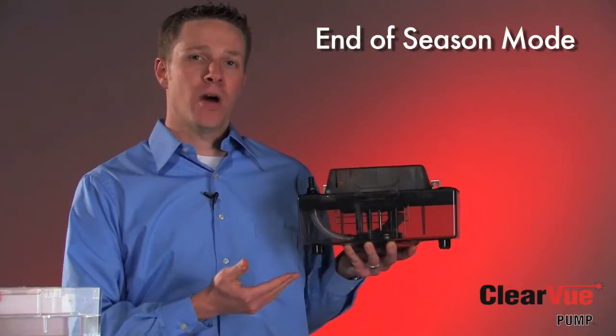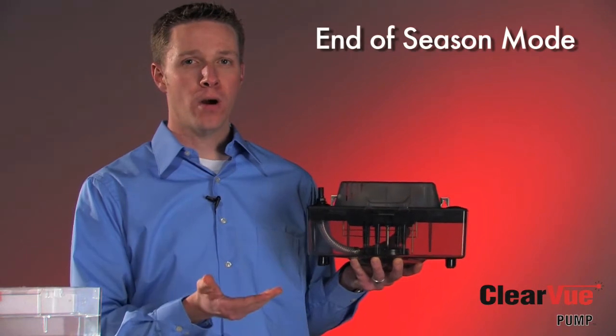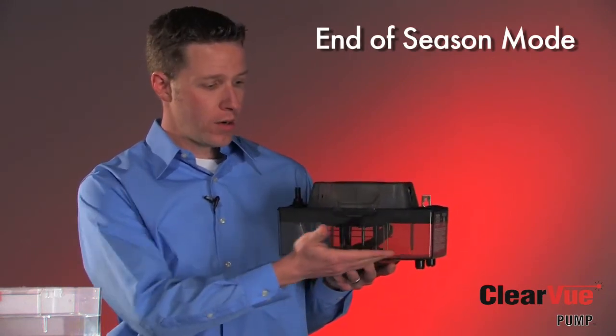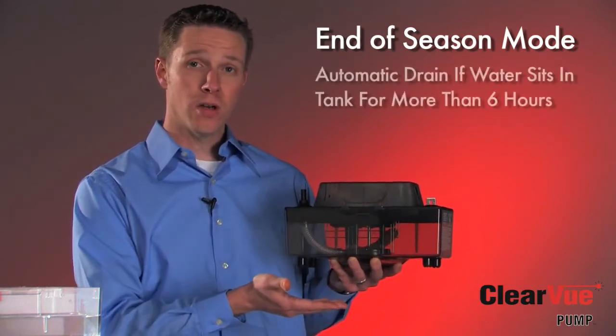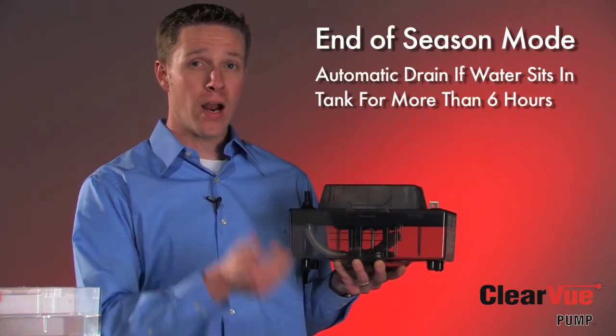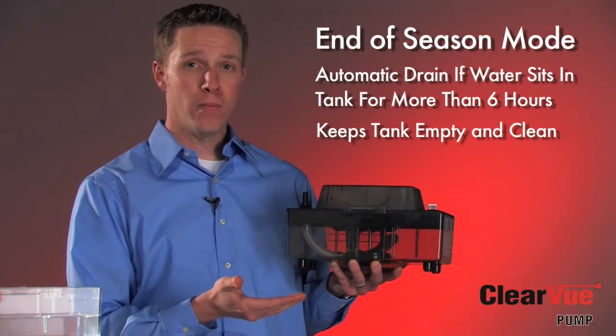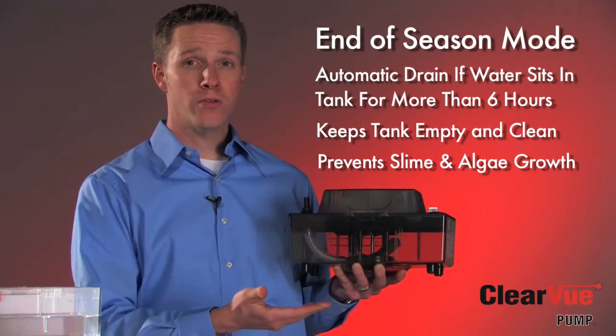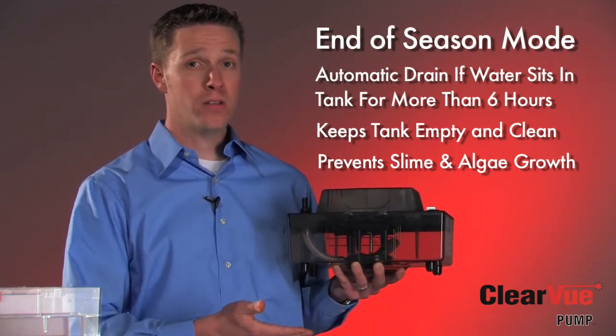The last feature I'd like to talk about with ClearVue is what we call our end-of-season mode, another part of our IQ technology. Basically, if water has remained in the tank for a period of six hours or more while touching the bottom sensor, ClearVue knows to run a pump-down cycle to get that water out of the tank to prevent any slime or algae buildup inside the tank. So with ClearVue, it's almost 100% dry all the time, especially between seasons or periods of not cooling.